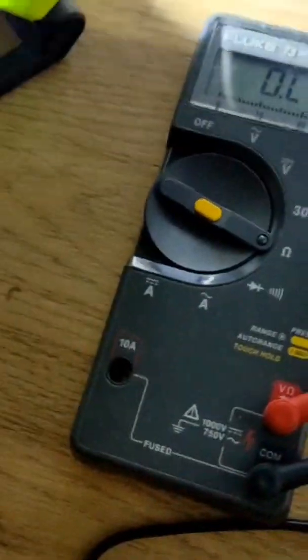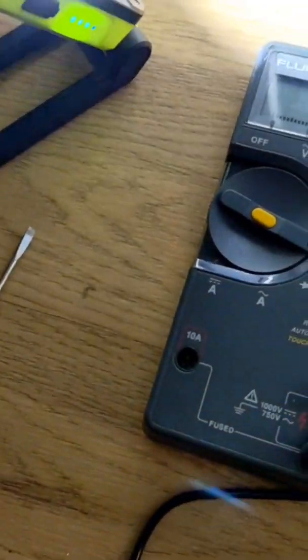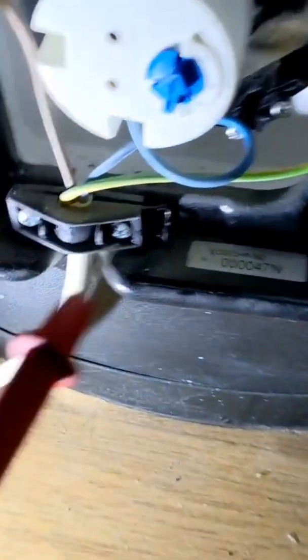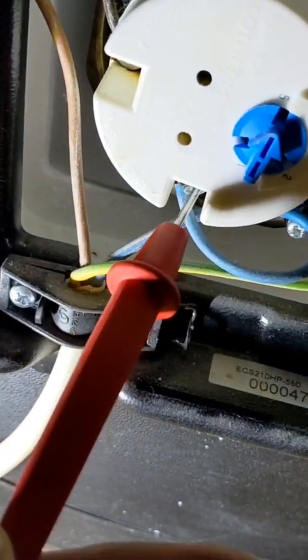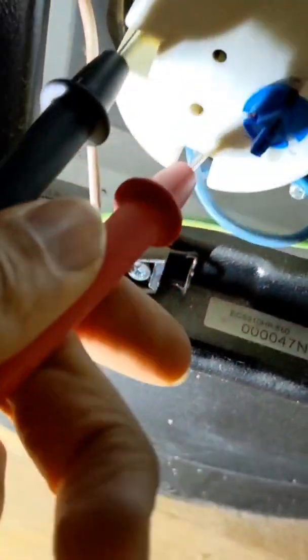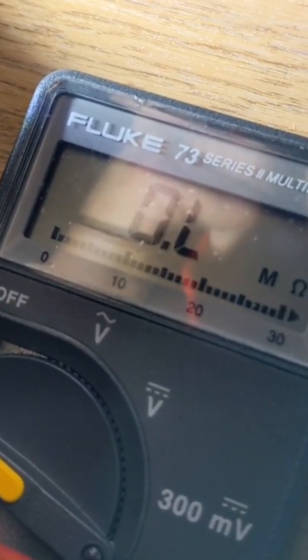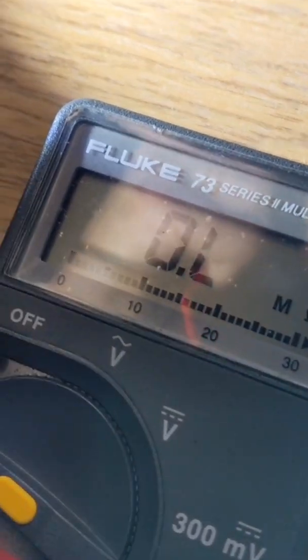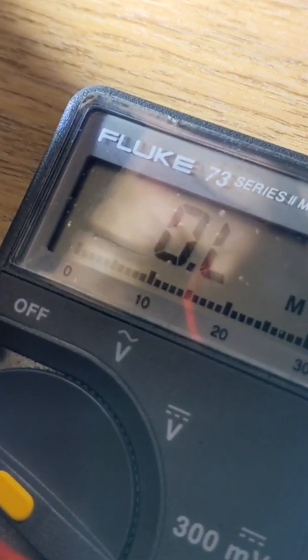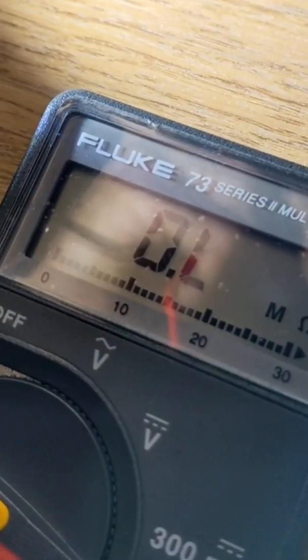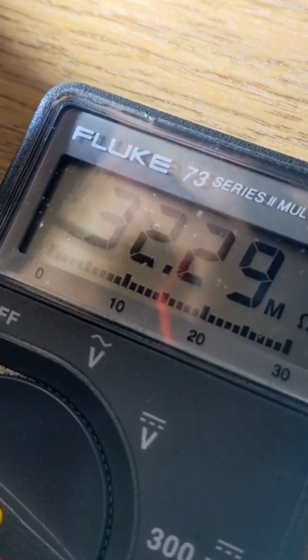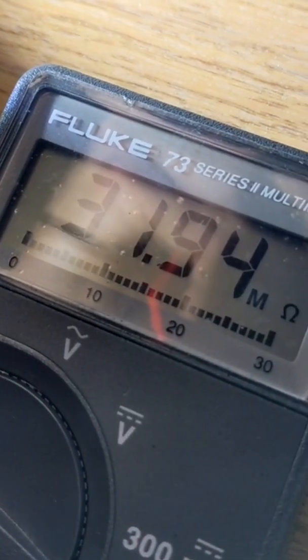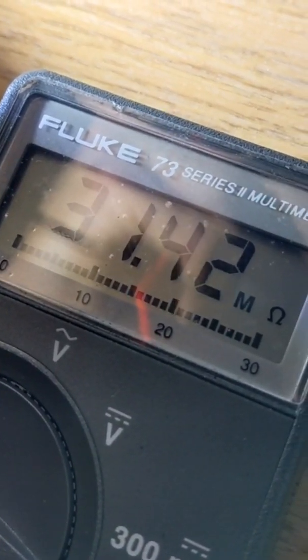Get your multimeter out, set it to ohms, and then first what you want to do is check between live and neutral with the power off. I've got open line. That should be reading 20 ohms or thereabouts, so the resistance is not there. That means the immersion is faulty, or you're going to get a stupid figure like that, 32 mega ohms.